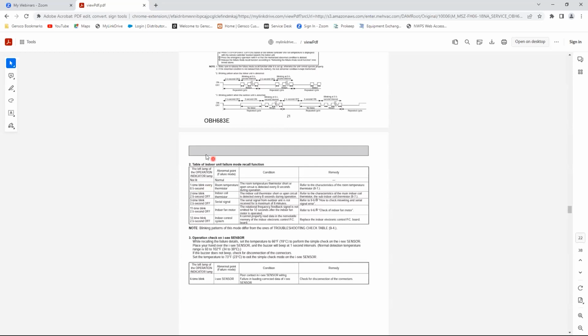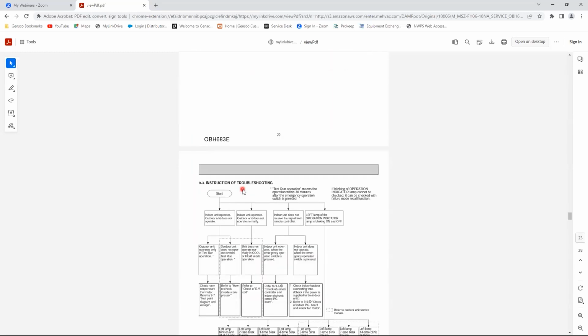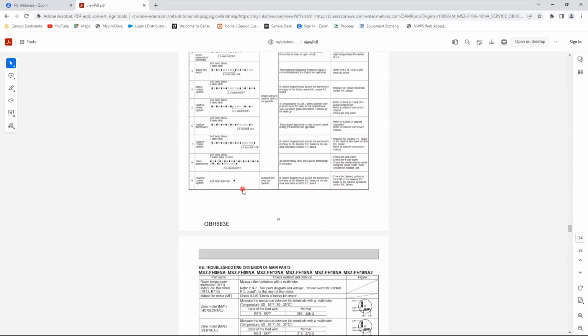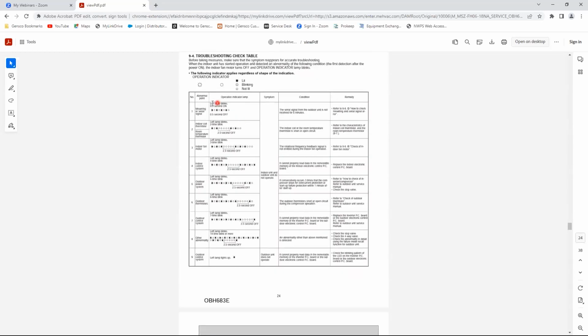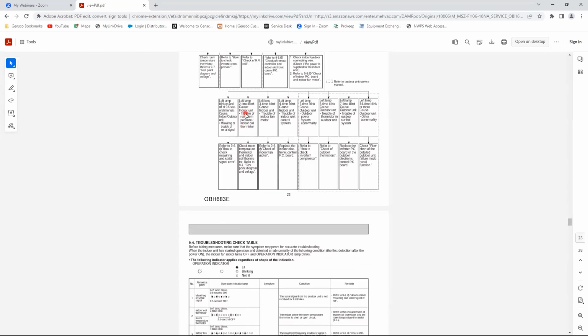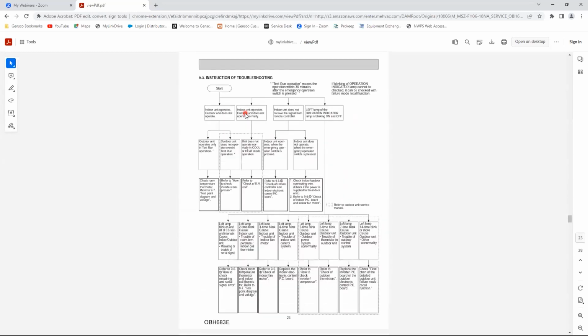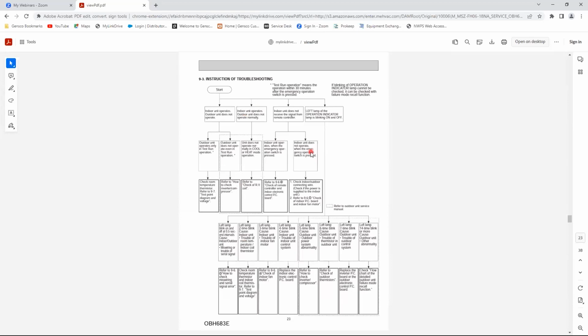Okay. So you'll see here that if you do the failure recall mode and you get a 1 flash, that is a room temperature thermistor error. But if I scroll down here to the active error, a 1 flash is a miswiring or serial signal error. So be conscious about which table you are using and what method you get your error code from. Here's a troubleshooting flow chart.